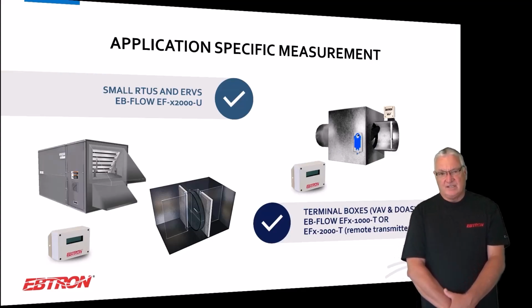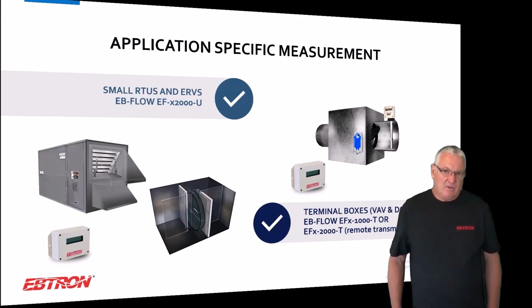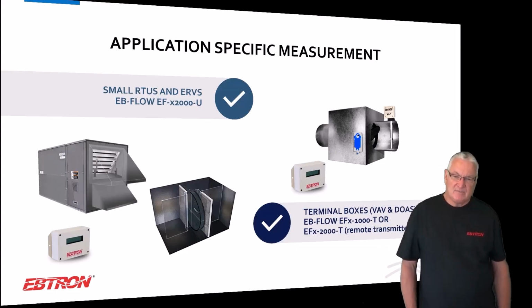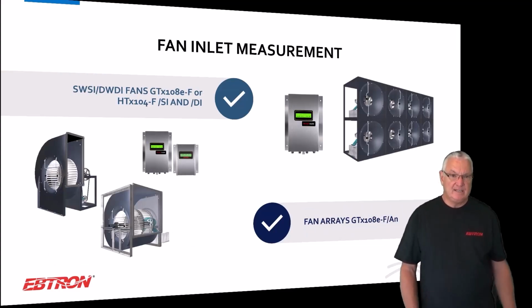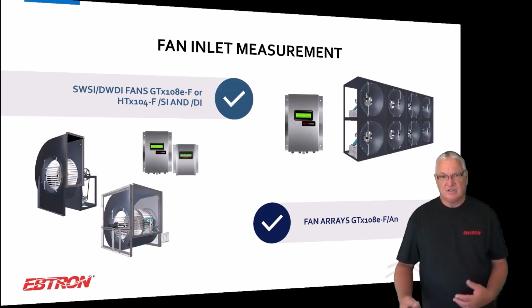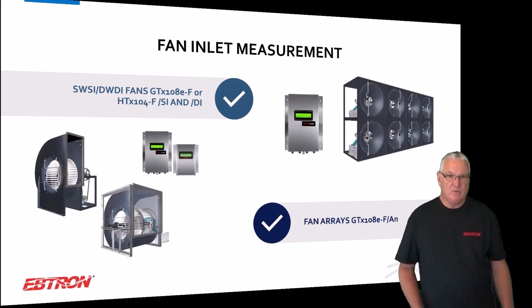You can use these devices on terminal boxes. Sometimes people will use them on VAV boxes to get more turn down on traditional type VAV or labs. We'll also use them for tracking on smaller duct systems. They're perfect for most of your DOAS applications. It's basically a stripped down version of the EBTRON, okay? And so it's something you should look at and make sure you understand that we have, okay? Fan inlet measurement. We have devices that are designed for single and dual inlet fans as well as fan arrays, okay? So that might be something that you want to measure.